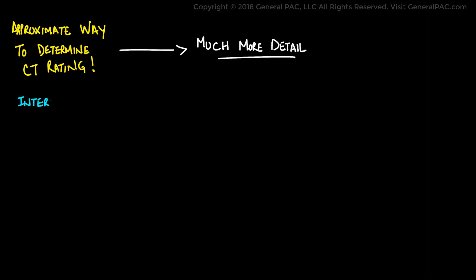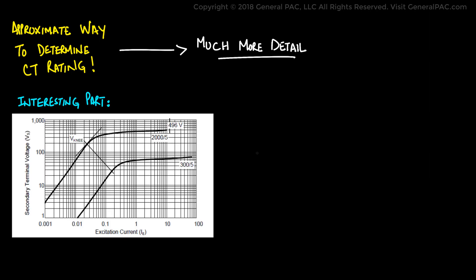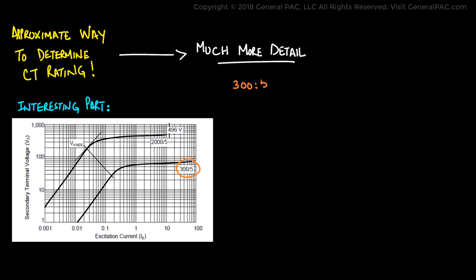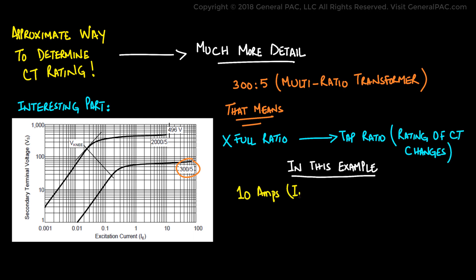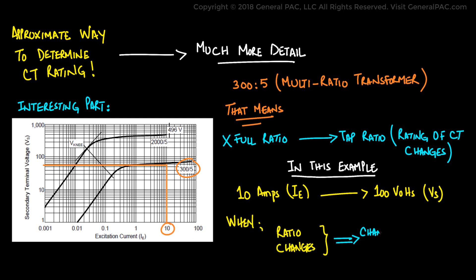The second curve, ratioed at 300-to-5, is part of the multi-ratio current transformer. If we are looking at a ratio that is not the full ratio — meaning it's a tapped ratio — then the rating of the current transformer changes. In this example, at 10 amps exciting current, the voltage is definitely less than 100 volts. So as we change the ratio, we also change the CT rating quite considerably — keep that in mind.